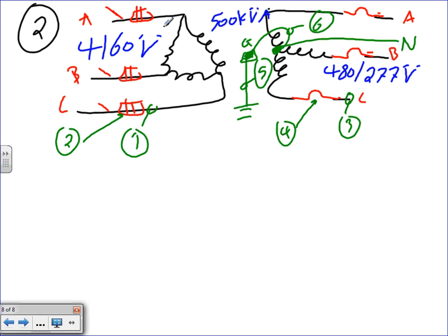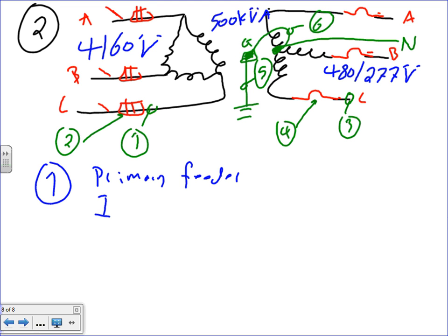All right, let's start with number 1. Number 1, we need to size. Now this is a primary feeder, guys. We're gonna size the primary feeder. I primary equals the 500 kVA divided by 1.73 times 4160. This is 4160 volts. Very commonly used voltage.